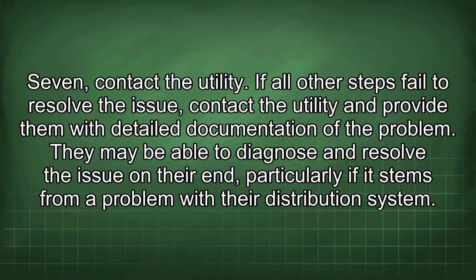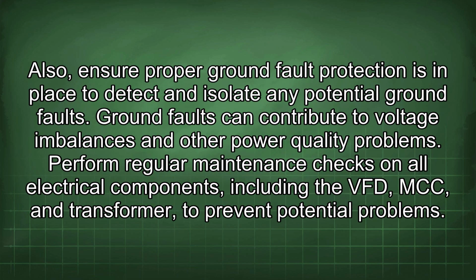7. Contact the utility. If all other steps fail to resolve the issue, contact the utility and provide them with detailed documentation of the problem. They may be able to diagnose and resolve the issue on their end, particularly if it stems from a problem with the distribution system. Also, ensure proper ground fault protection is in place to detect and isolate any potential ground faults. Ground faults can contribute to voltage imbalances and other power quality problems.